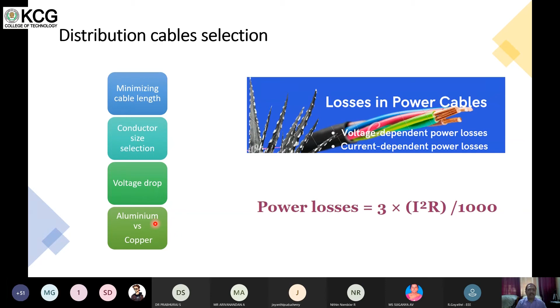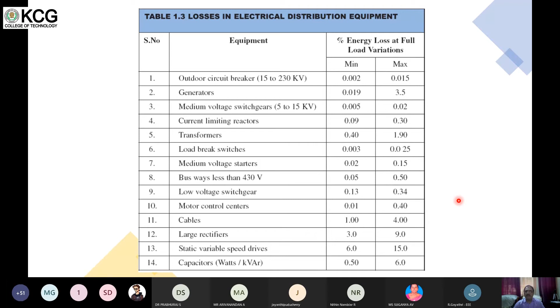I have a list for some of the losses in various equipment like outdoor circuit breakers, generators, medium voltage switchgear, and so on, where the losses are given in minimum and maximum. So what is maximum has to be reduced is what we have to understand from this. This is just a general commentary on various losses. As you can see, cable losses are between 1 to 4%. So our aim should be to bring it as close as possible to the minimum level by implementing a successful plan. Sometimes it's possible for you also, as a new employee, to take this as an assessment area and bring it to the notice of some of your seniors and then ask for an investment budget so that you can upgrade what is already available.